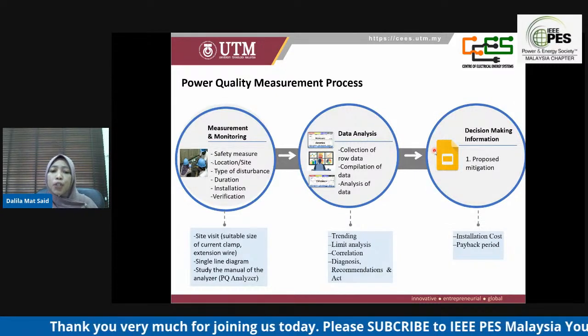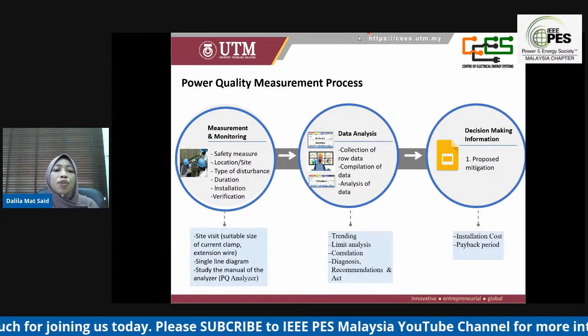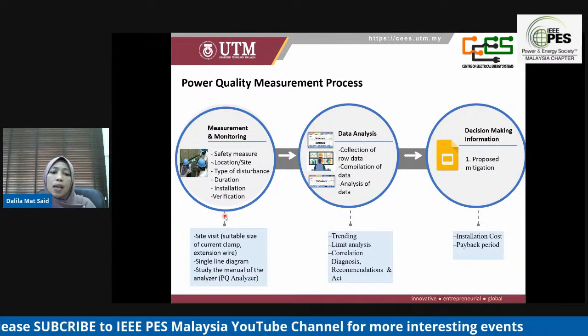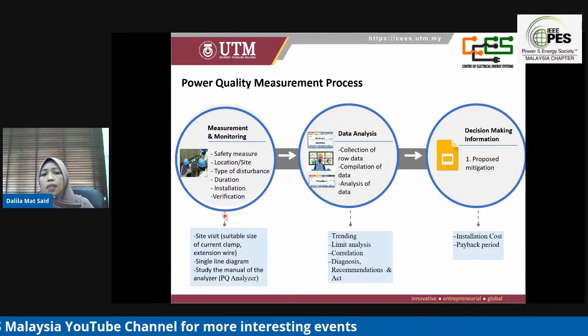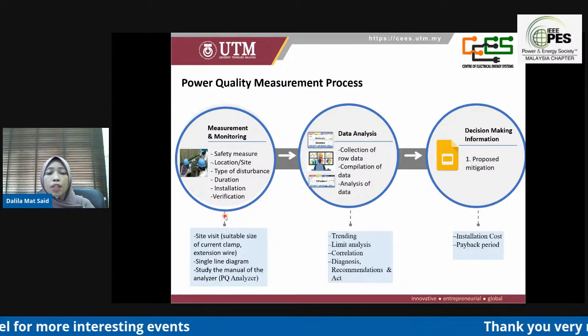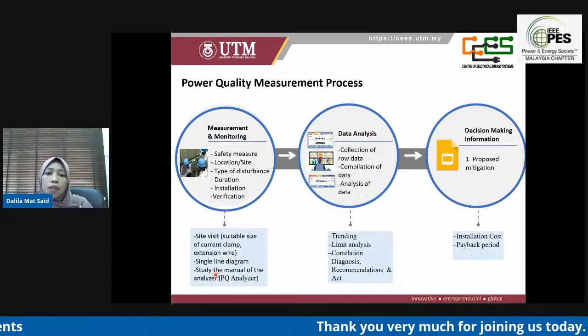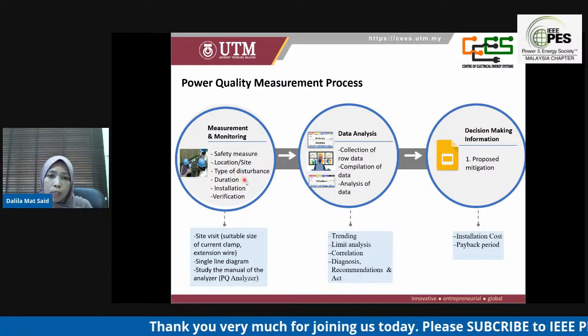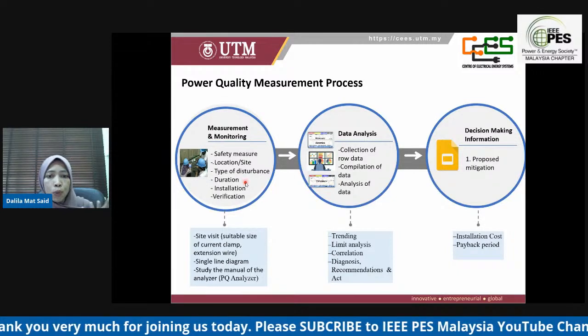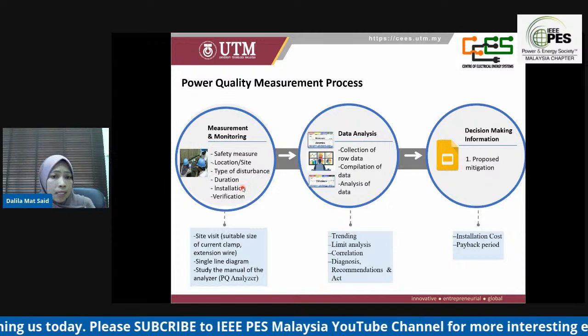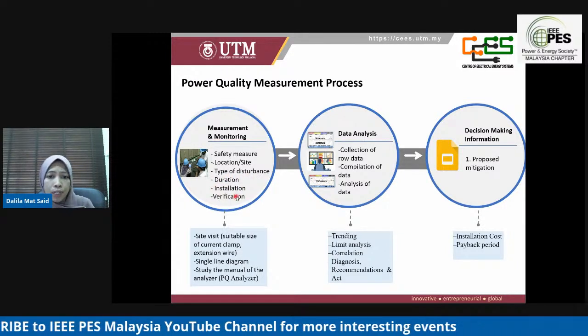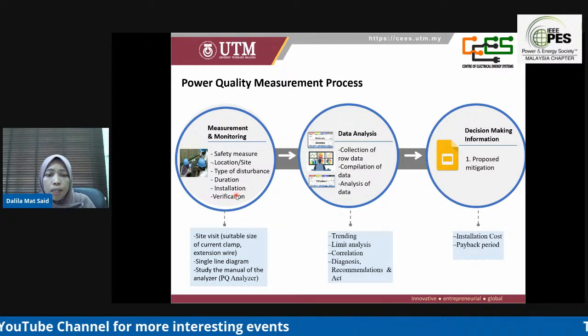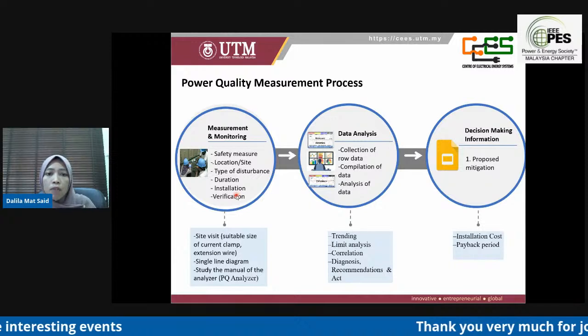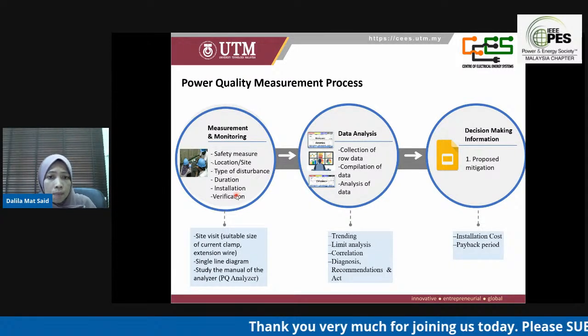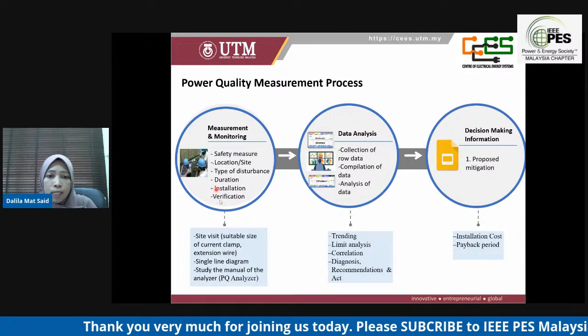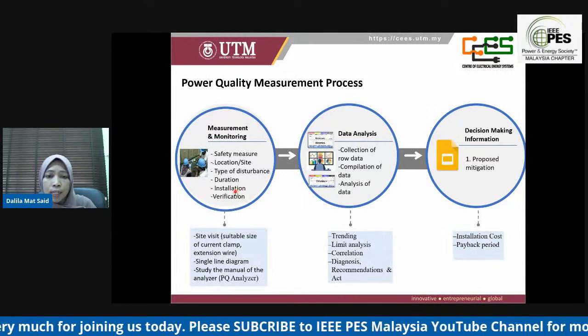So from the above discussion, I can summarize and conclude the process of measurement and monitoring power quality. A measurement of power quality requires the use of a proper instrument to suit this application. The user of the instrument must be well trained in the use and care of the instrument. Starting with the measurement process, we need to consider the safety measures, where we want to install the device, and the type of disturbances that we need to capture, because we want to know the duration. If this is only a steady state, it is enough to install for about 1 week at a 10-minute interval. If this is an instantaneous event such as a voltage sag, maybe we need to install for about a month or a year, depending on the situation. And of course, the verification and checking after the installation.